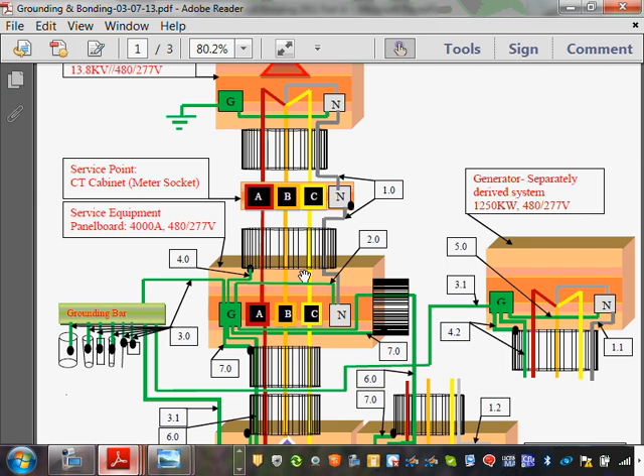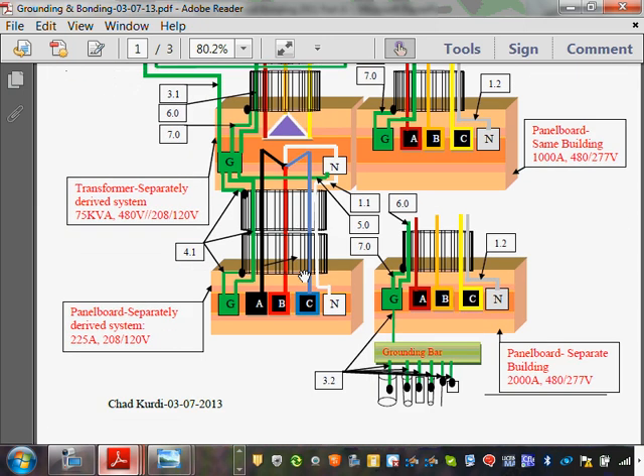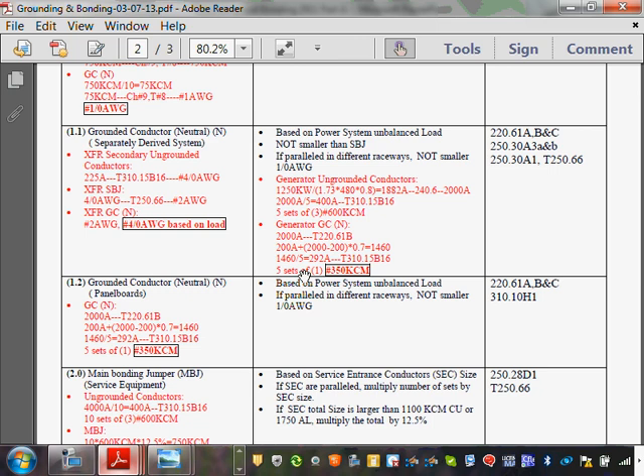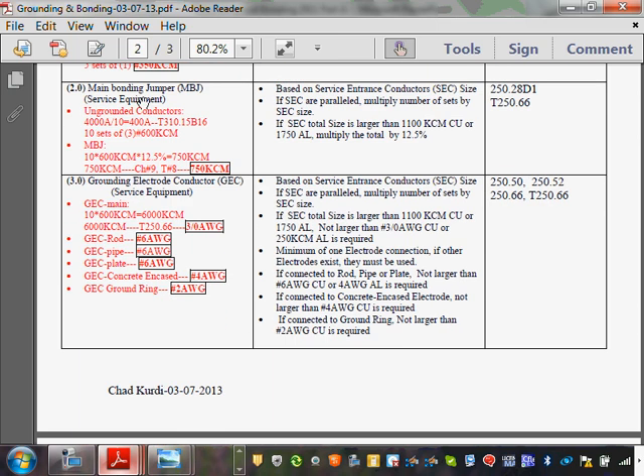So do me a favor, I'm going to go size. I grounded the system, I grounded my enclosure, my box, through my grounding electrode system. So I'm going to go size 3. Let's look at how we size 3. If you go all the way to number 3, that will be the first page, right here, the bottom of the first page. I know they're flipped. 3.0. This is called the grounding electrode conductor. Here's all the information on how to size it, guys.